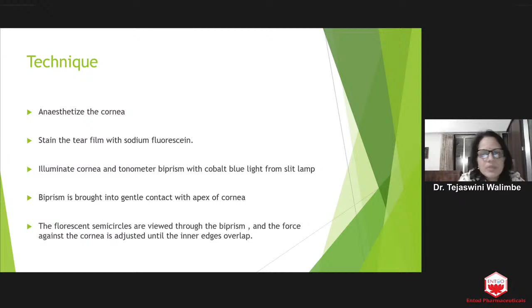We should not press too much and too little. So that we should see the mires properly, and they should be symmetrical. Up means up, above and below, both the mires should be symmetrical and same in size. And once we see the mires, I will show the diagrams and everything. So we have to adjust the scale so that the inner borders of the upper and lower mires coincide. The fluorescent semicircles are viewed through the biprism, and the force against the cornea is adjusted until the inner edges overlap. So this is the diagrammatic presentation of the mires in Goldmann applanation tonometry.